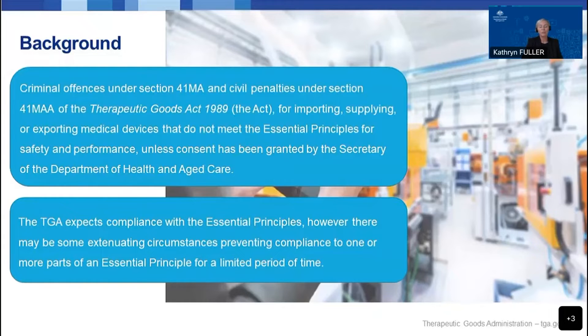The TGA will review the risk of supplying the non-compliant medical devices with consideration to the risk mitigation strategies that the sponsor or manufacturer are going to put into place. It should be noted that if your non-compliant medical device is currently part of an application to vary the device or manufacturer's evidence, or you have an application for inclusion in the ARTG and the device is going to be supplied whilst non-compliant with the essential principles, you will still need to apply for consent.